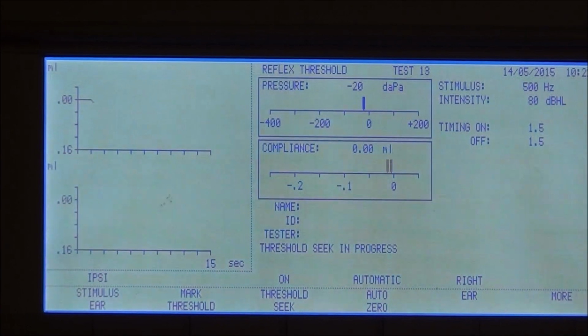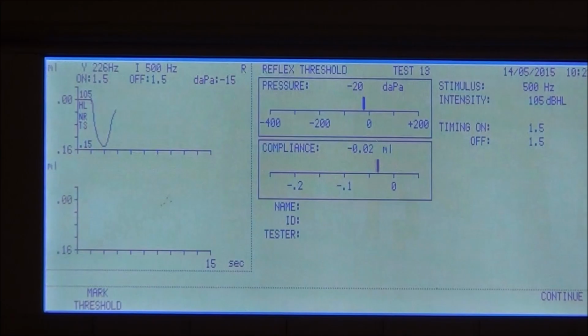You see what happens. The instrument does it automatically. 70, 75, 80, 85, and it is looking for what? Minimum 0.03 reduction. Will it come? That's quite a large change. My scale itself is 0.1. Did you get it? So there is a reflex, but the instrument is not considering it as.